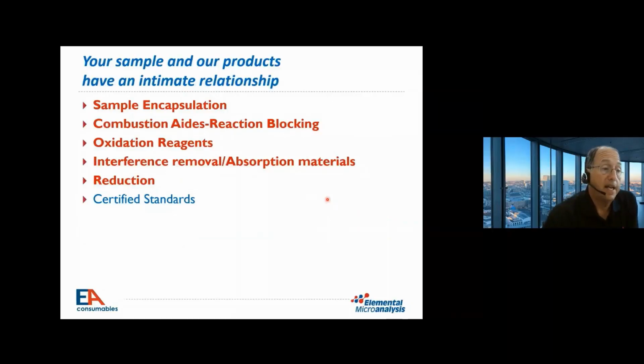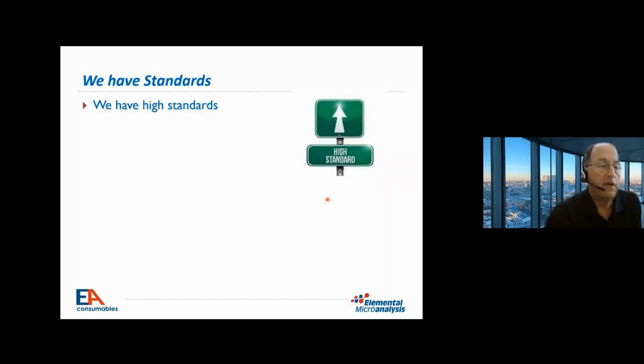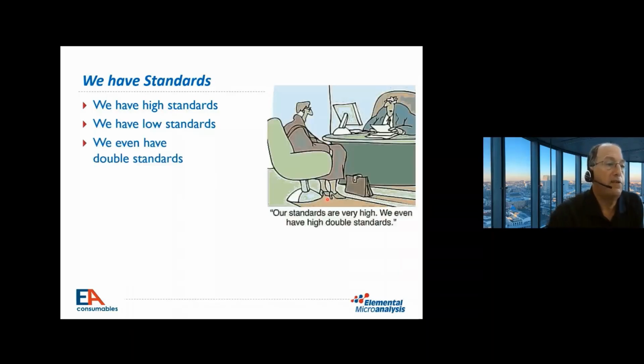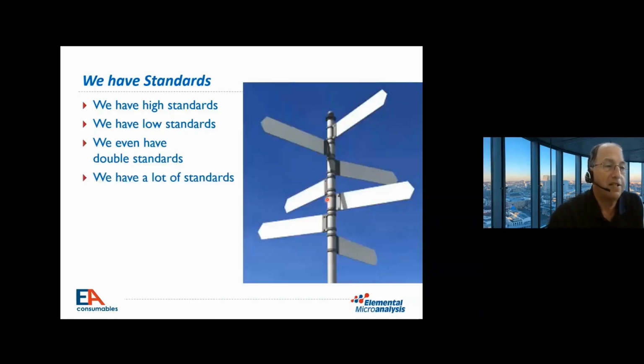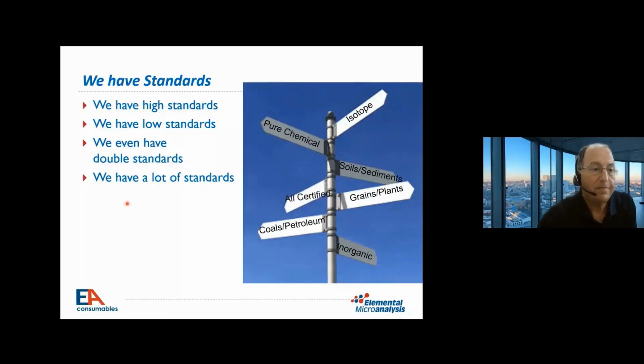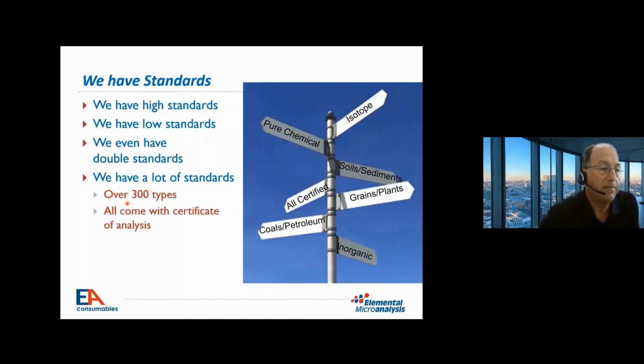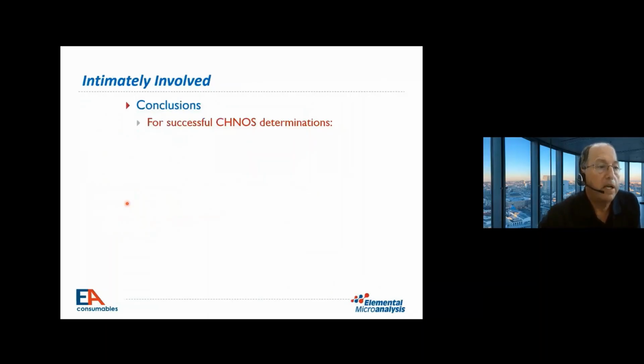And finally, certified standards. We mentioned before that the TCD detectors do have to be calibrated, so you need standard materials of known composition to do that. We have high standards and low standards, and we even have some double standards, but the bottom line is we have a lot of different standards, and they're all certified, over 300 different types, and all come with a certificate of analysis traced back to NIST.